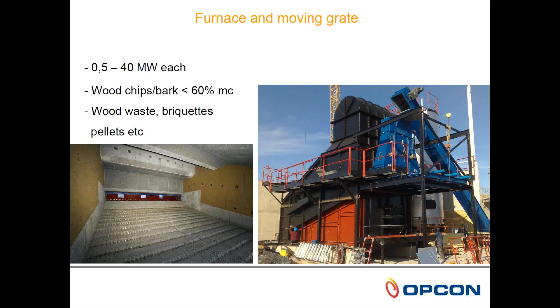When combusting moist fuels, a lot of the energy is in the flue gas that will be waste if it's just let out directly. But with a flue gas condenser, we can recover the energy in the flue gases. It can be up to 20 to 30% of the energy input that we can recover. And in our flue gas condenser, we have a special setup for this. It's at the same time a flue gas cleaner, so we are reducing the amount of dust in the flue gas. So in the same machine, we both recover energy and clean the flue gas from dust. As you see here, we are cleaning it from 250 milligrams down to 100, or down to 20 milligrams if we are also using the wet electro filter after this condenser.